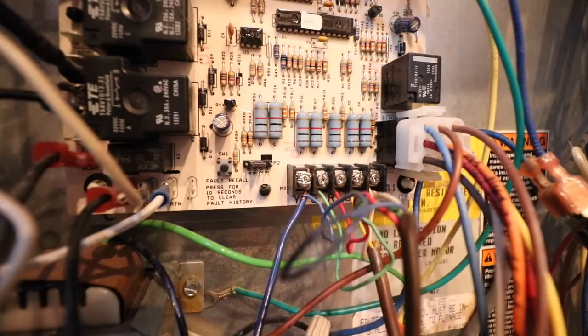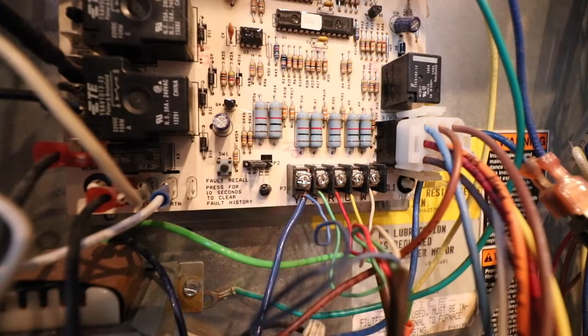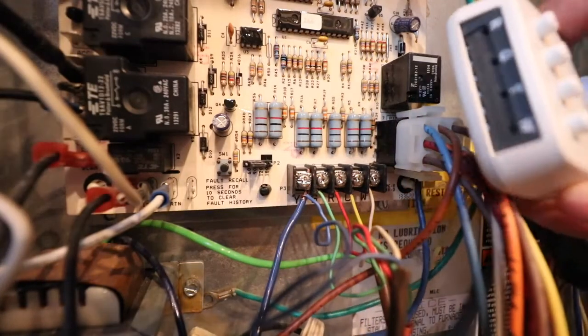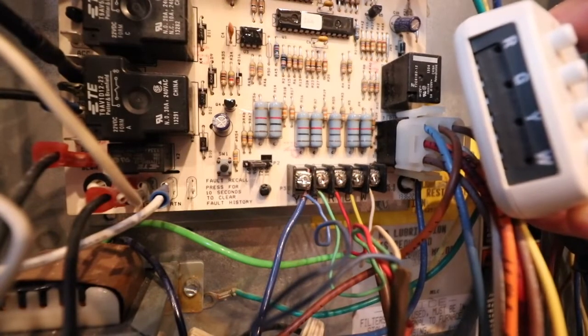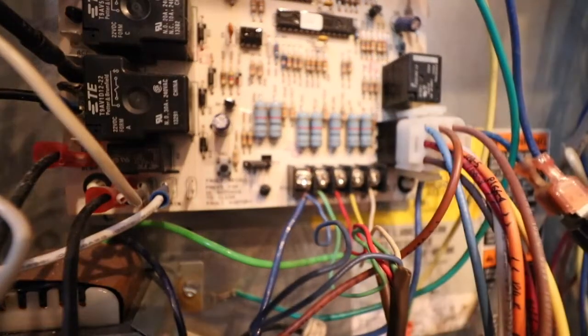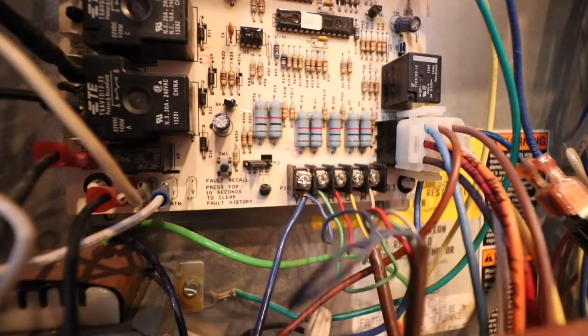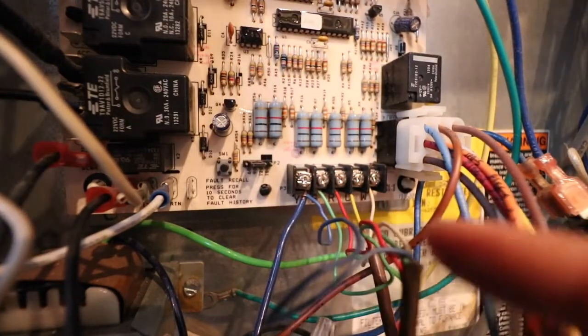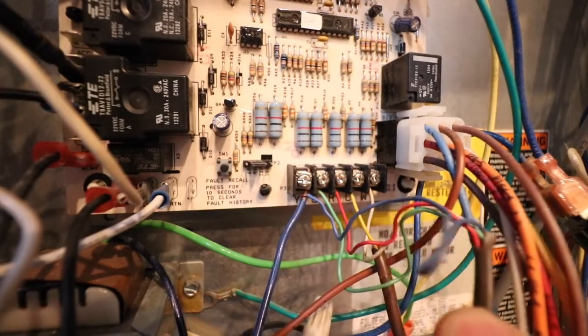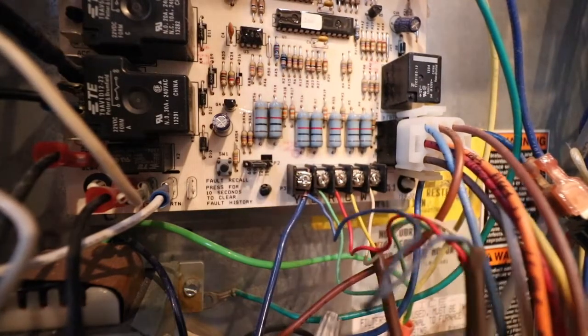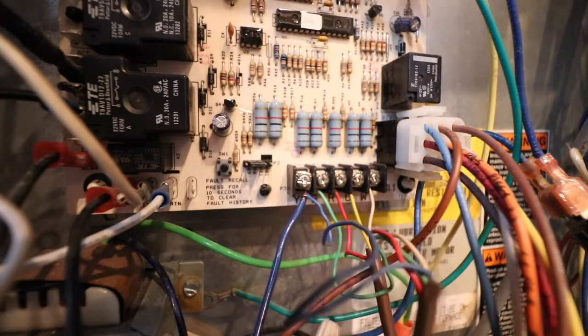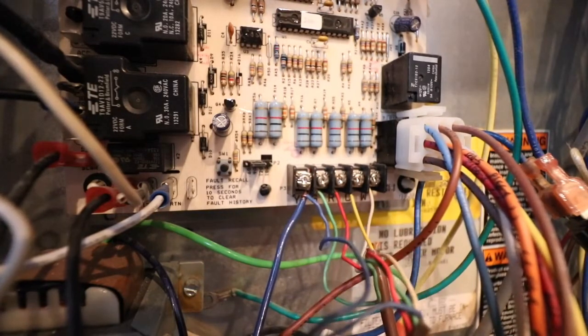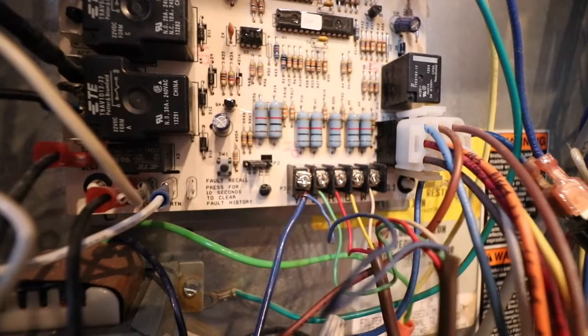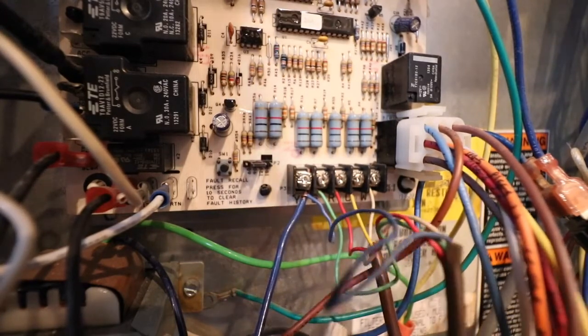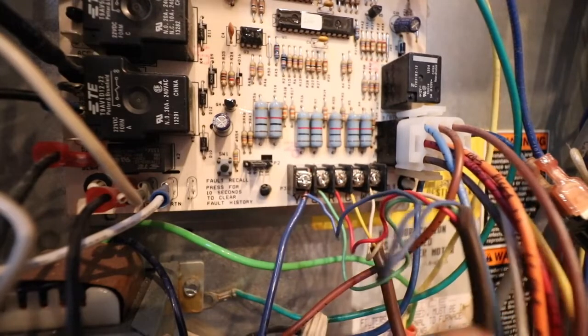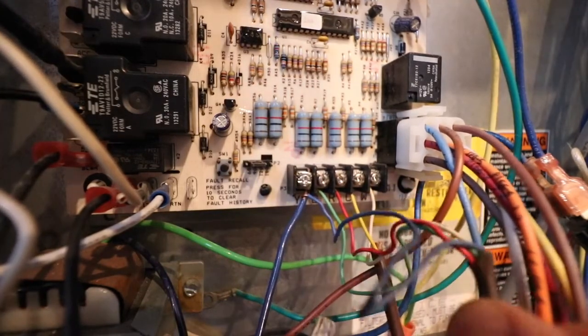Now, what's important to note is that the wires that you want to remove, that will then go in the bottom of the Ecobee common wire adapter, which we've got here with the terminals down at the bottom, are the wires that are all coming from the thermostat in one bundle. So we have this 4-wire bundle coming through in the thermostat wiring, and this goes all the way back to the thermostat. And typically you're going to be able to trace this out of your HVAC system, and it will go up into a wall or into a conduit and then to your thermostat. So make sure that the wires you're disconnecting all come from one bundle that is coming from the thermostat.